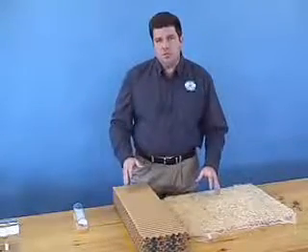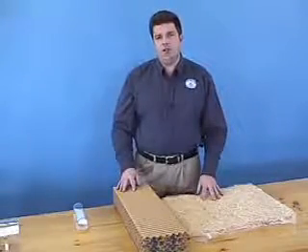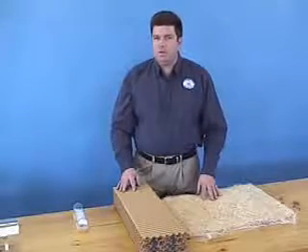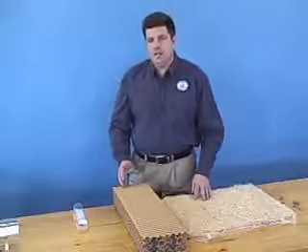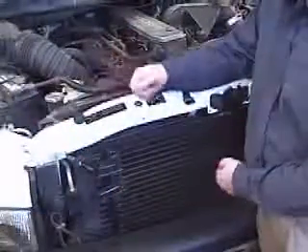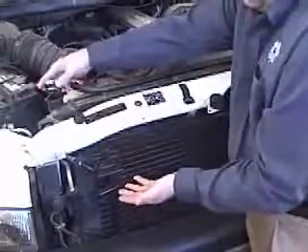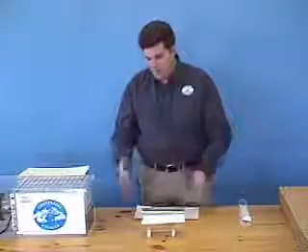Indirect evaporative coolers use the principles of evaporation, but do not add any moisture to the air entering the building. An indirect evaporative cooler utilizes a heat exchanger. A common example of a heat exchanger is the radiator in a car. The hot liquid in your car's radiator transfers heat to the air outside without the air from the outside getting in, or the hot liquid from the inside getting out. The same heat exchange principle is true for an indirect evaporative cooler.